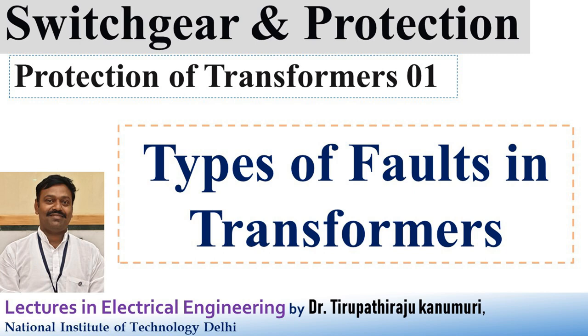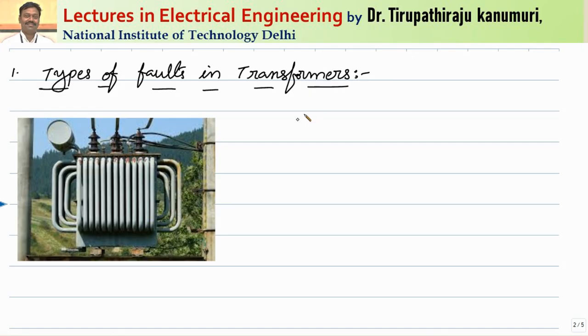Today we are going to discuss different types of faults that happen in the transformer, meaning we are going to introduce the protection of transformers. Generally a transformer is a static device because it doesn't have any rotating parts, and in most cases it is sealed and immersed inside oil. Outside there will be a conservator tank, and generally a Buchholz relay is used for transformers greater than 500 kVA.